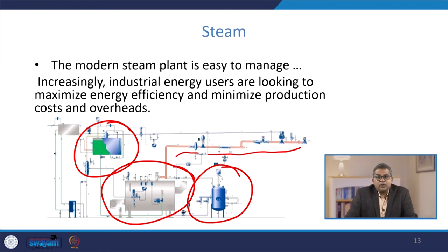Now, the role of the blow down tank is that repeated use of water may create the formation of scale or sludge. Now, these scale or sludge do not possess any kind of heat value or heat transfer facilitation aspect. So, these need to be removed intermittently to improve the energy efficiency as well as the boiler efficiency. So, intermittently these sludge or scales are removed over a period of time through this blow down valve. We will discuss this in a later part.